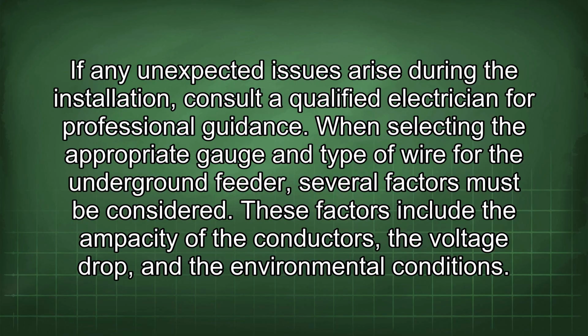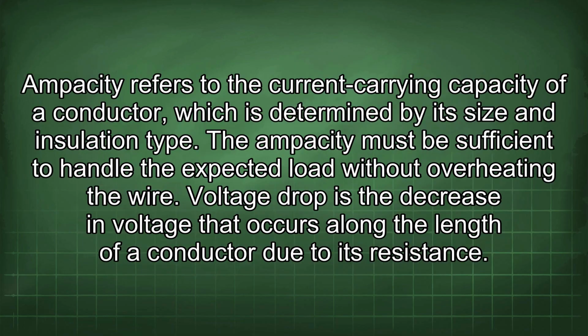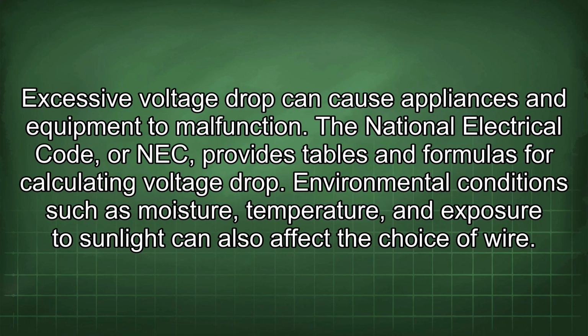When selecting the appropriate gauge and type of wire for the underground feeder, several factors must be considered. These factors include the ampacity of the conductors, the voltage drop, and the environmental conditions. Ampacity refers to the current carrying capacity of a conductor, which is determined by its size and insulation type. The ampacity must be sufficient to handle the expected load without overheating the wire. Voltage drop is the decrease in voltage that occurs along the length of a conductor due to its resistance. Excessive voltage drop can cause appliances and equipment to malfunction.